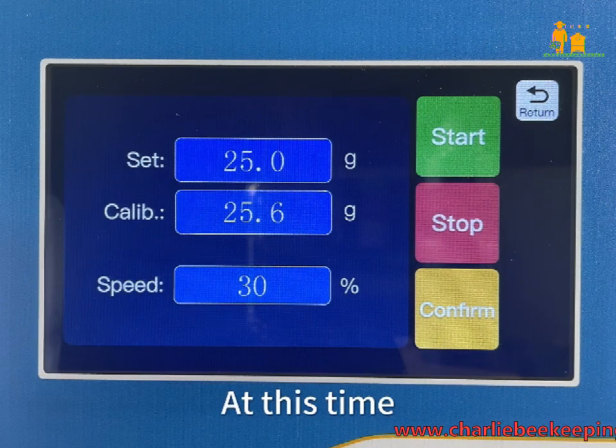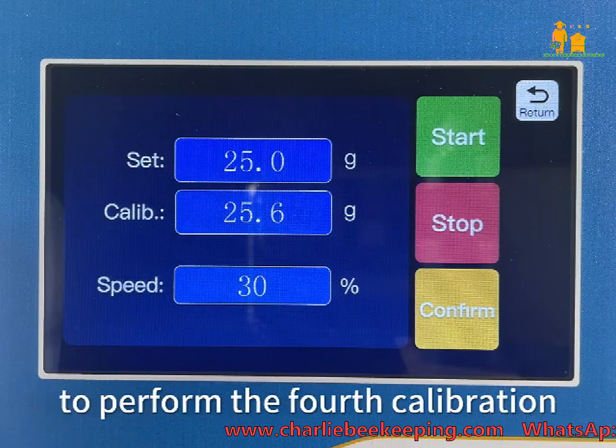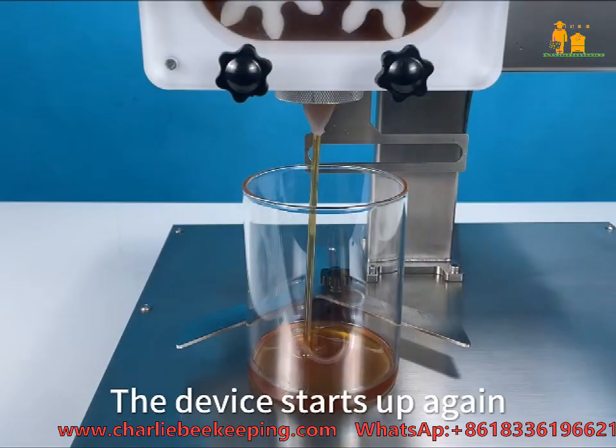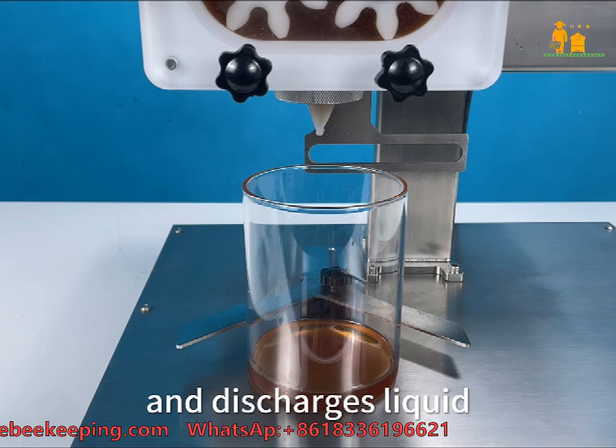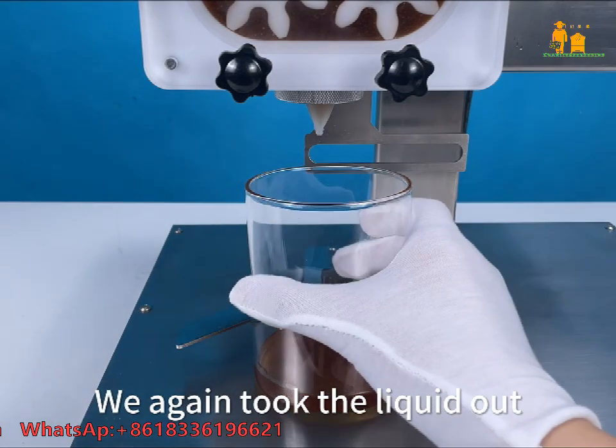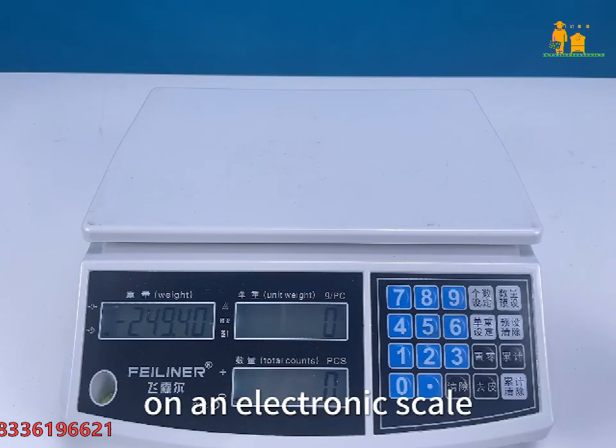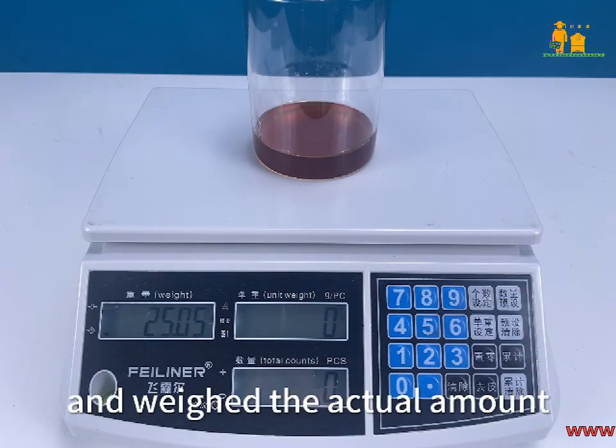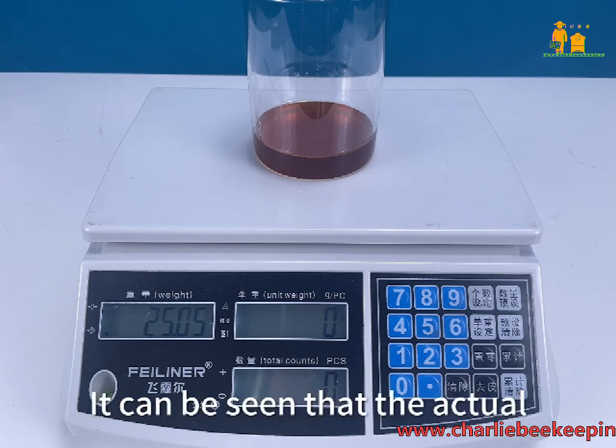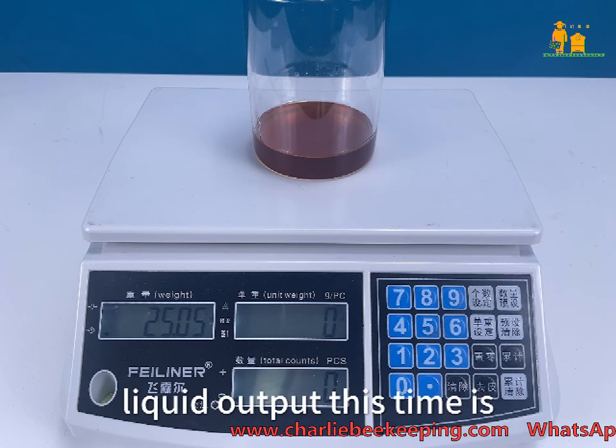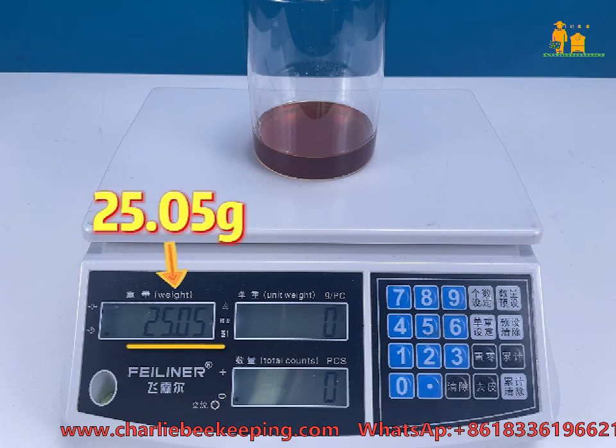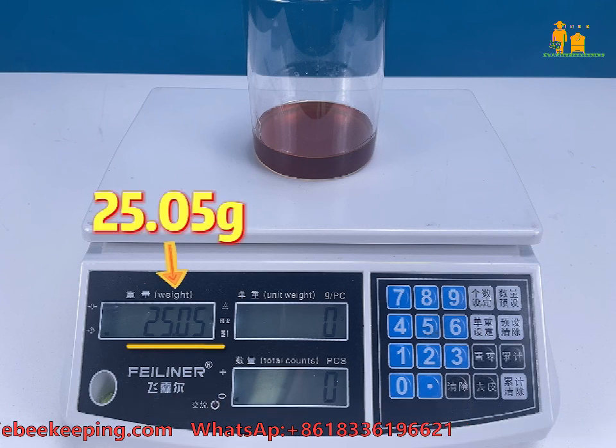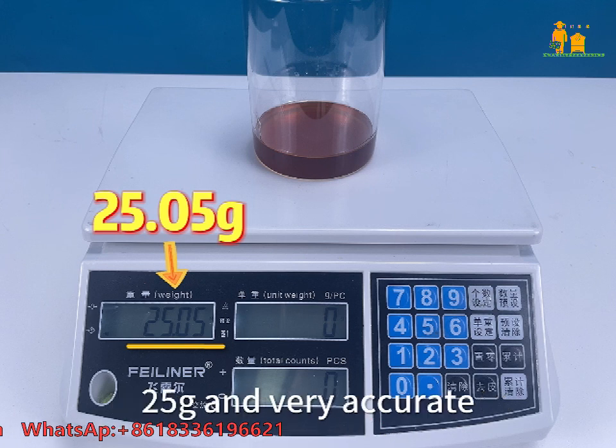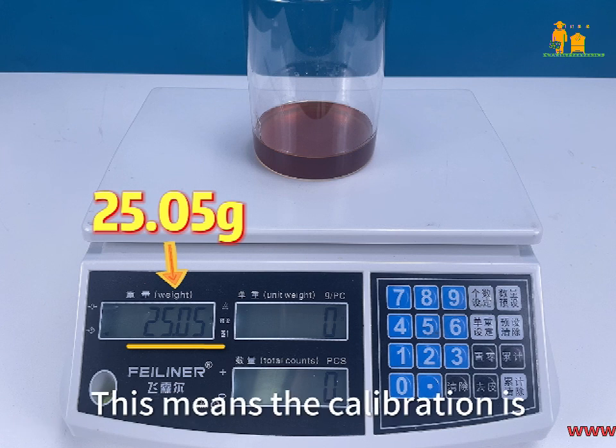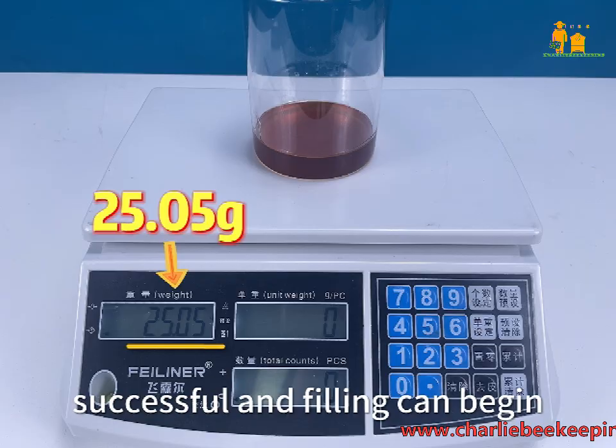At this time, click the Start button again to perform the fourth calibration. The device starts up again and discharges liquid. We again took the liquid out on an electronic scale and weighed the actual amount of liquid output. It can be seen that the actual liquid output this time is 25.05 gram. This weight is very close to 25 gram and very accurate. This means the calibration is successful and filling can begin.